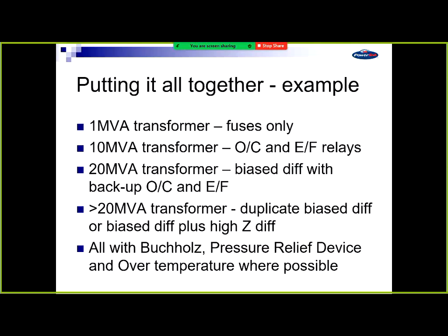So if we pull all of this together then, for the 1 MVA transformer, we only use fuses. At 10 MVA, you can use an overcurrent and earth fault. At 20 MVA, a bias diff, and often they're then also done with an overcurrent and earth fault backup. Greater than 20 MVA, you can use duplicate bias diff or a bias diff and high impedance. And all of these have Buchholz, a PRD, and temperature as well, both winding and oil if possible, where you can do it. I'd also add in there that under the rules, it's voltage dependent, so not size of transformer dependent.